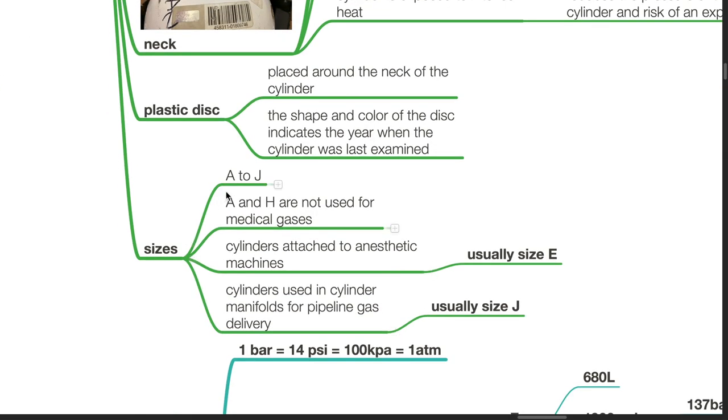Cylinder sizes range from A to J. A and H are not used for medical gases. Cylinders attached to anaesthetic machines are usually size E. Cylinders used in cylinder manifolds for pipeline gas delivery are usually size J.